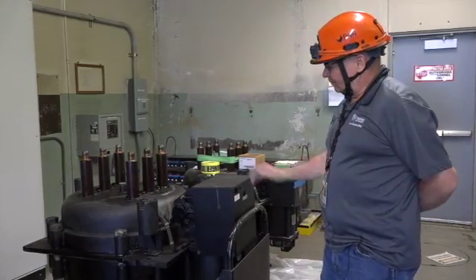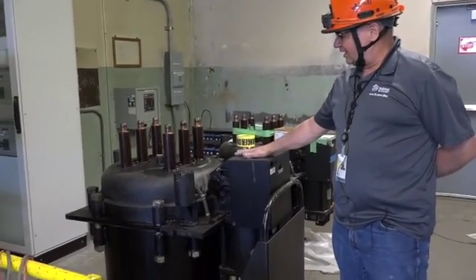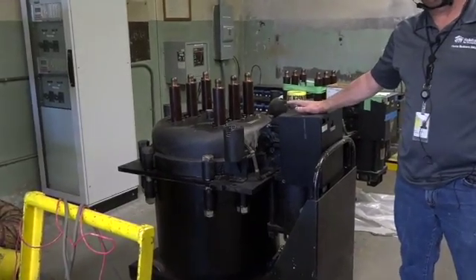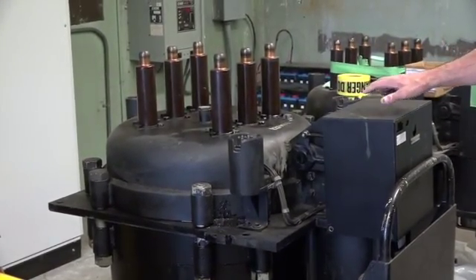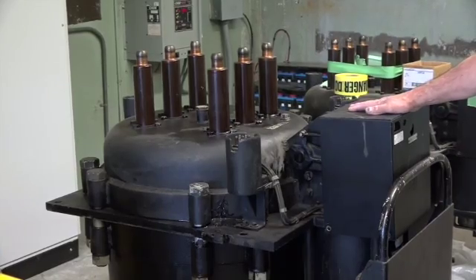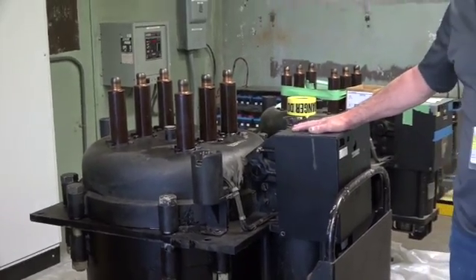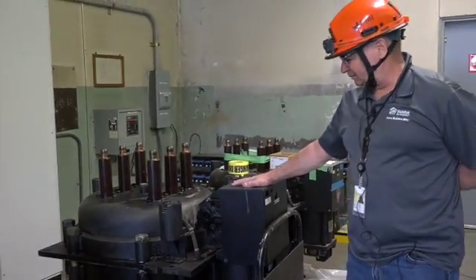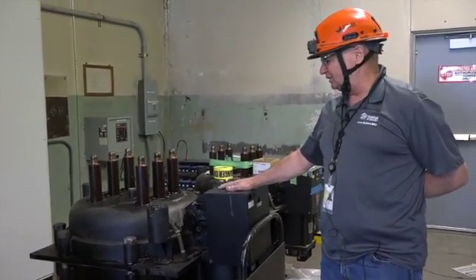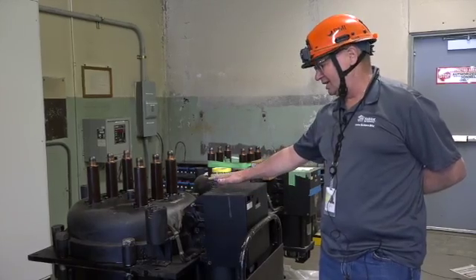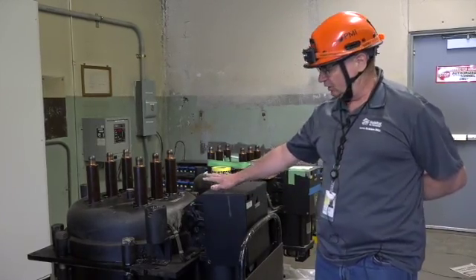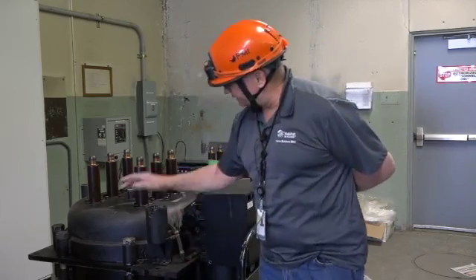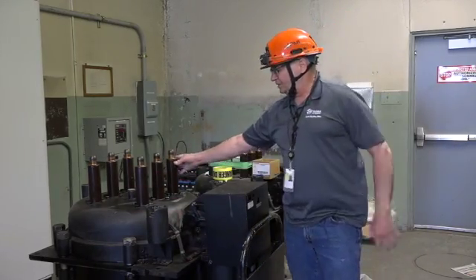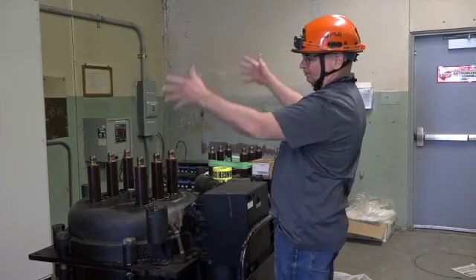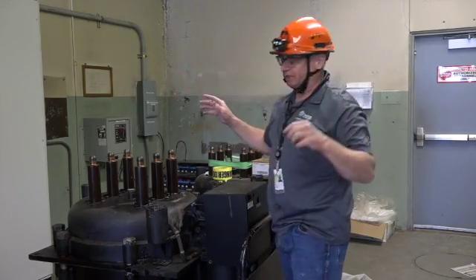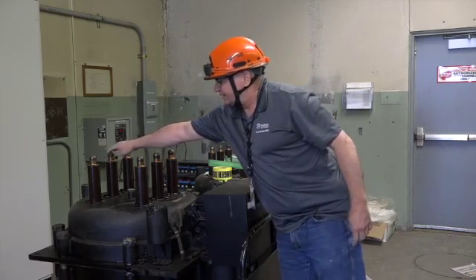This circuit breaker, you have circuit breakers in your house, in your electrical panel. This is a medium voltage circuit breaker. It's good for up to 15,000 volts, 1,200 amps. In electrical substations, this is a very old one. It's oil filled, and there's contacts inside. This whole circuit breaker lifts up into the substation gear and makes contacts.